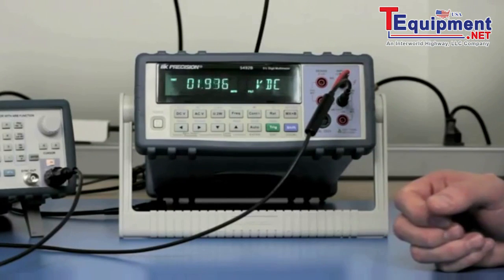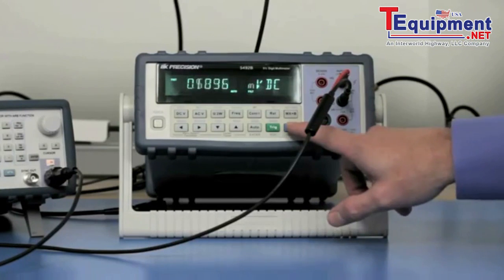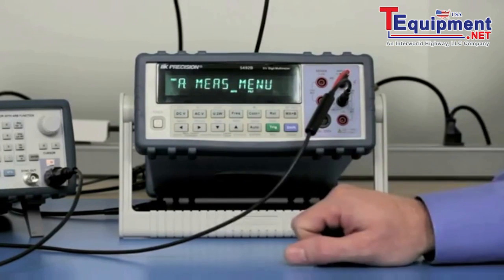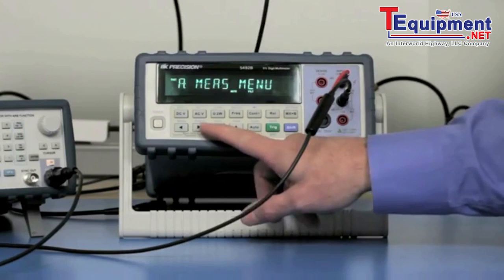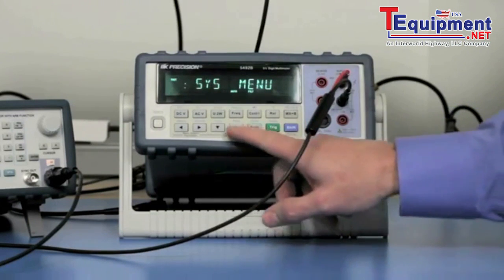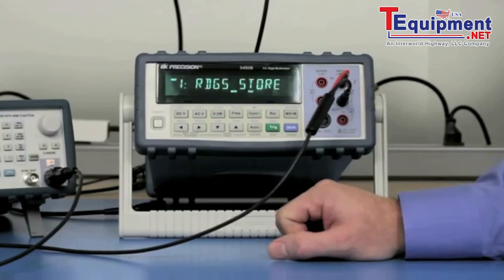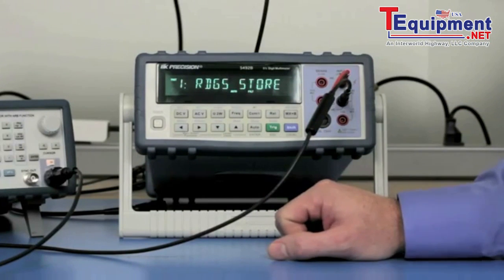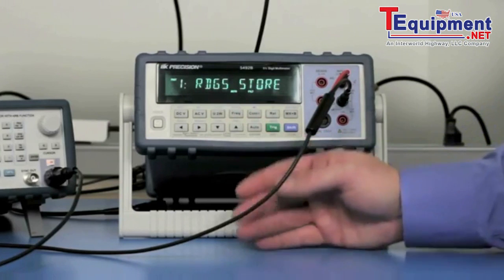To set up the 5492B to use the buffer storage operation, first we're going to press the Shift-Menu button. Then we're going to cycle through to the System menu. And this shows the readings stored. So here we're going to tell it that yes, we want to turn that on.